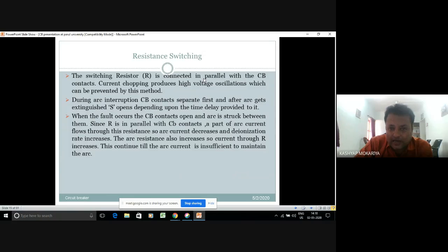So the switching resistor R is connected in parallel with the breaker. Current chopping produces high voltage oscillation, which can be prevented by this method. During arc interruption, circuit breaker contacts separate first, and the arc gets extinguished depending upon the time delay. So time delay has to be properly evaluated. When the fault current occurs, the circuit breaker contacts open and an arc is struck between them. So R is in parallel with the CB contacts.